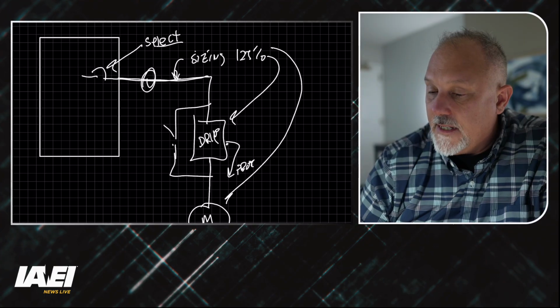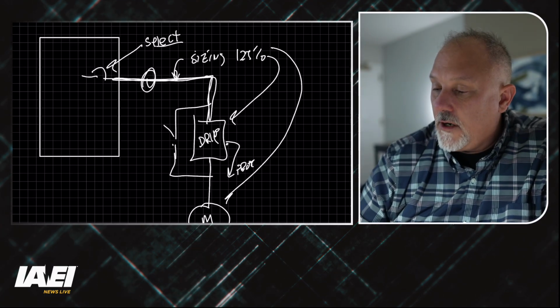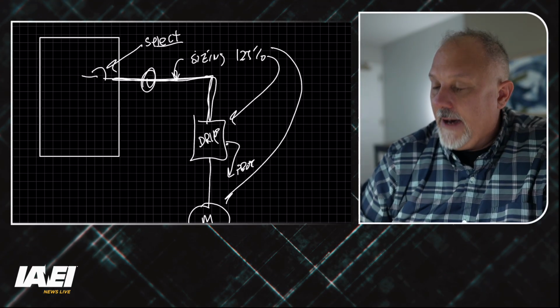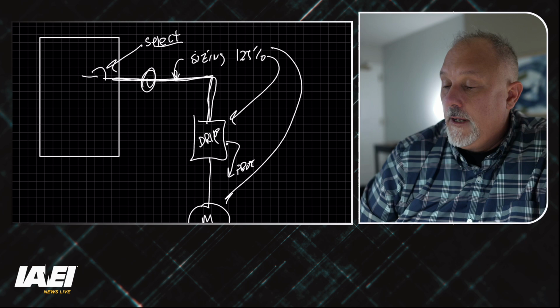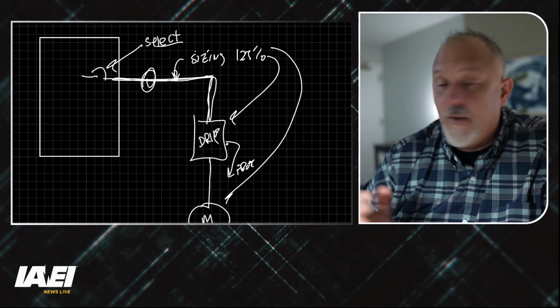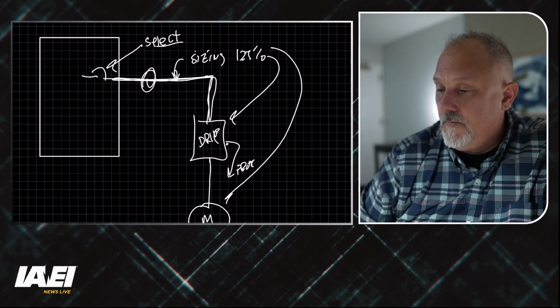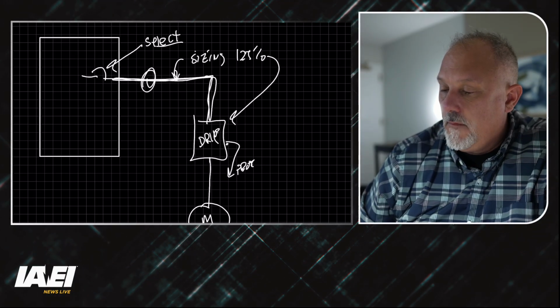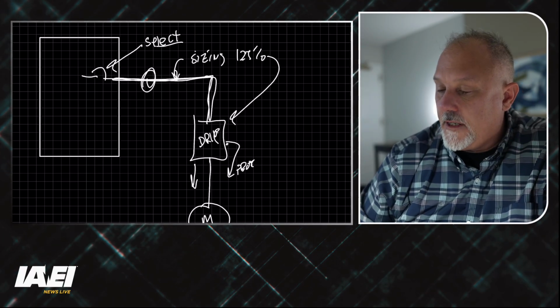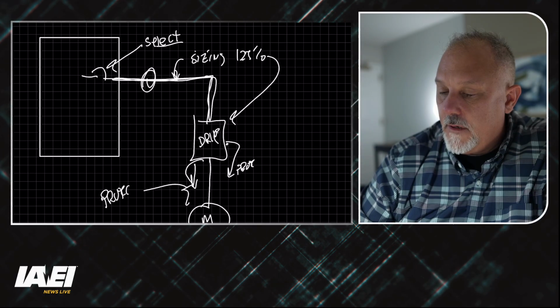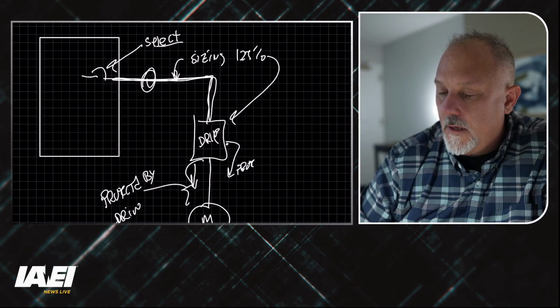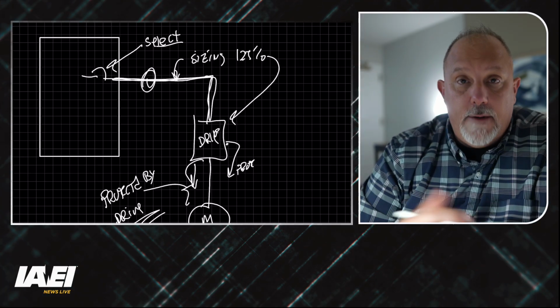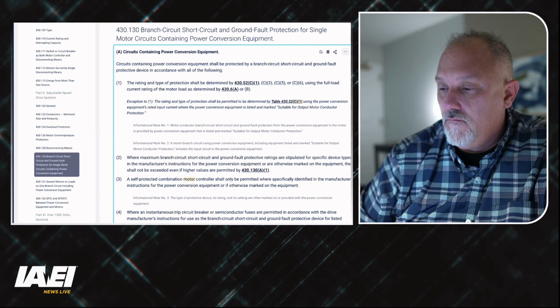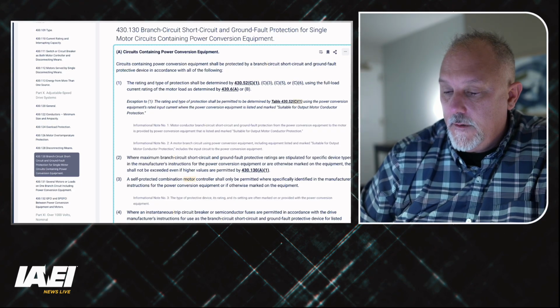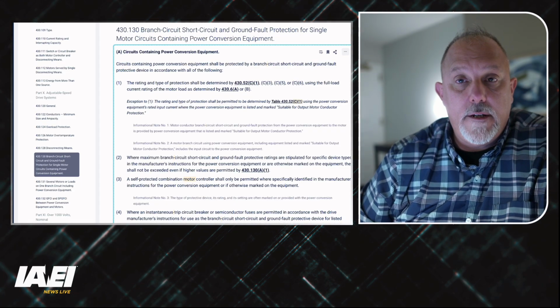And I would say if I'm sizing this circuit based on 125% of the drive, let's take the bypass out of the picture, then I protect it at its ampacity. I don't have inrush currents. I don't have to worry about fault currents coming back. And then the drive gives me the protection of these conductors. So this is protected by the drive. The moment I put a bypass in, now it's a different story. But I'm telling you, in my humble opinion, this is as clear as mud.